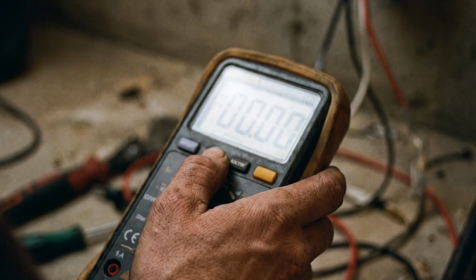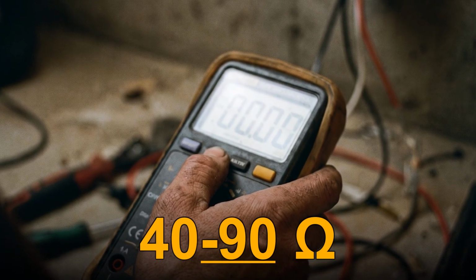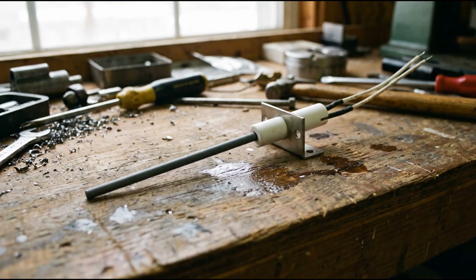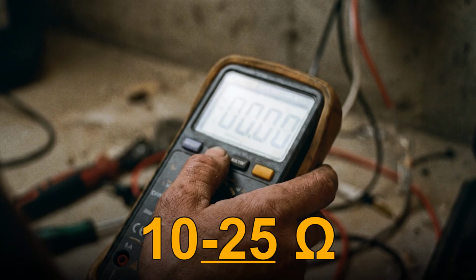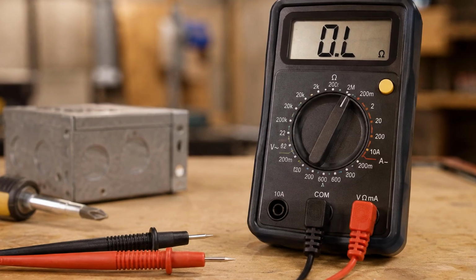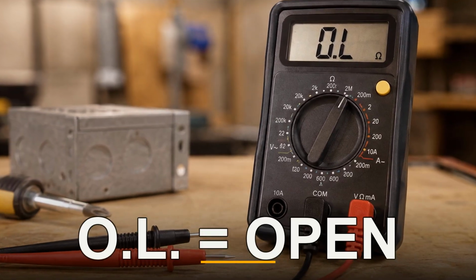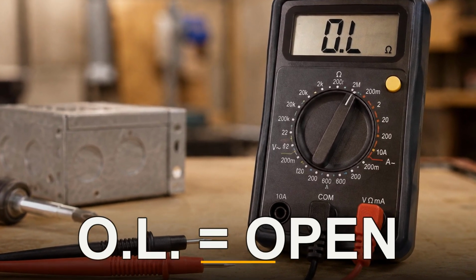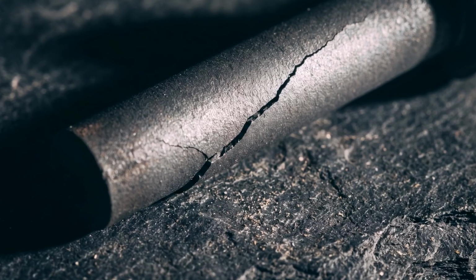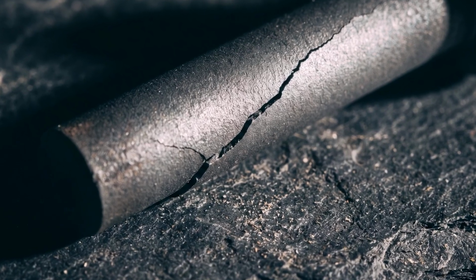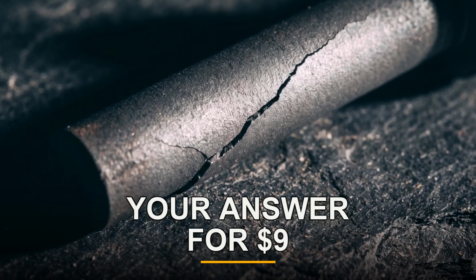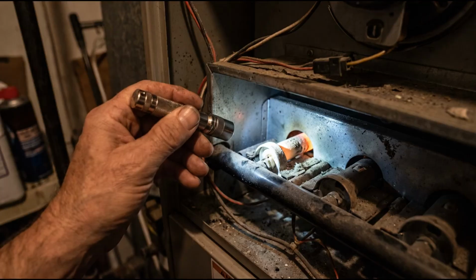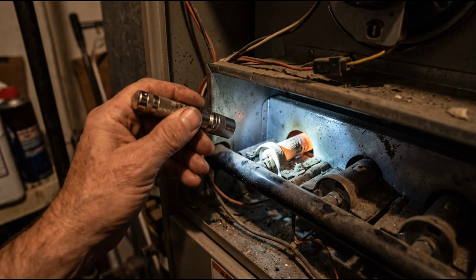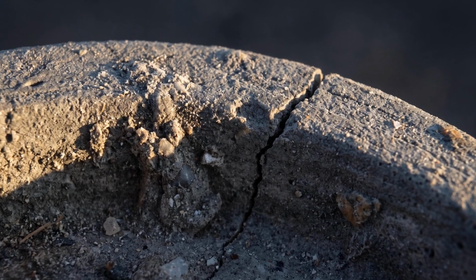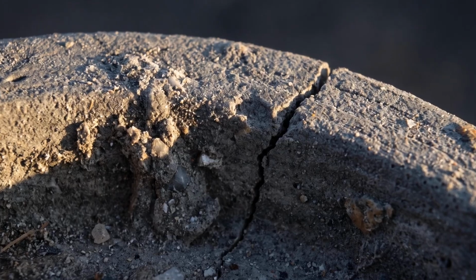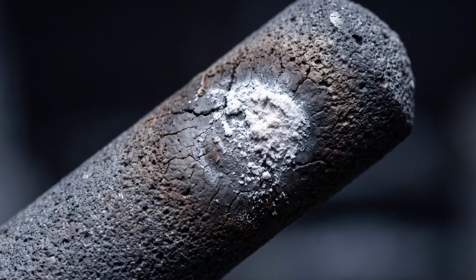A flat fork-style igniter should read somewhere between 40 and 90 ohms. The slim rod style reads lower, roughly 10 to 25. If your meter reads OL or shows nothing at all, no matter how you hold the probes, that igniter is open, cracked inside, dead. That is your answer in black and white for $9. And while you are in there, look at the element itself. A visible crack, a blister, a white burn spot, any of those confirms it.